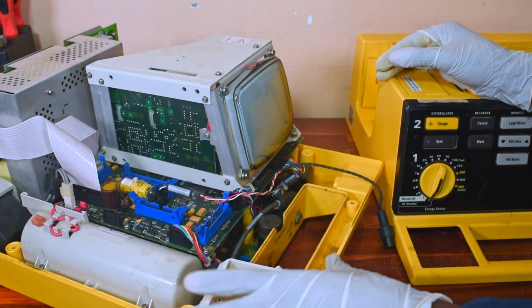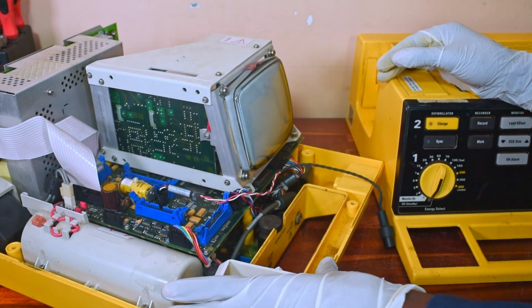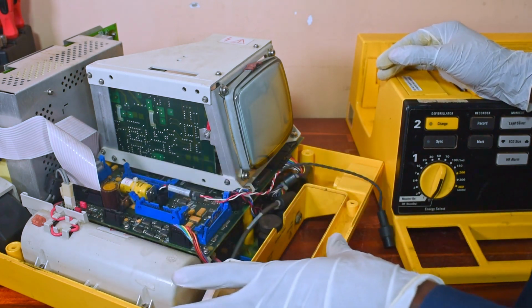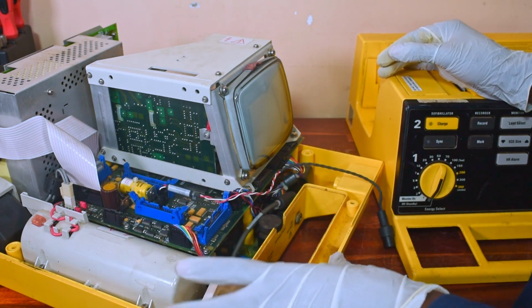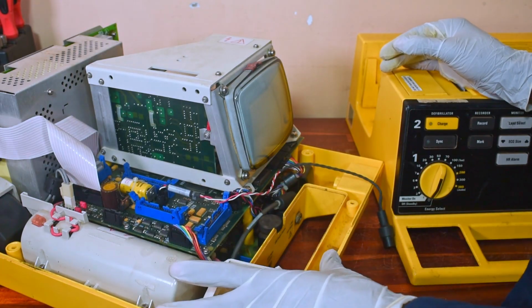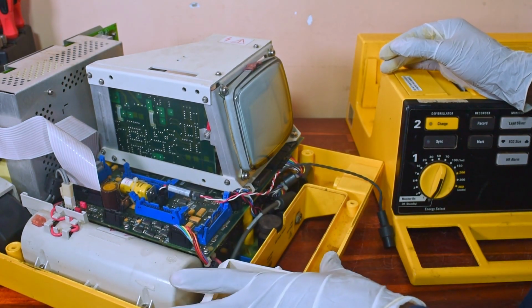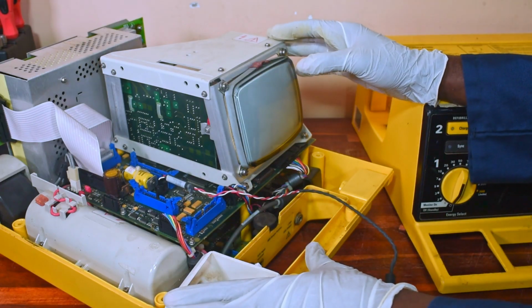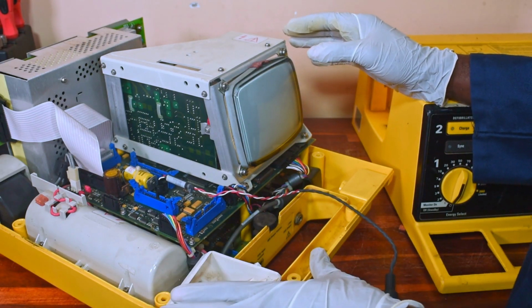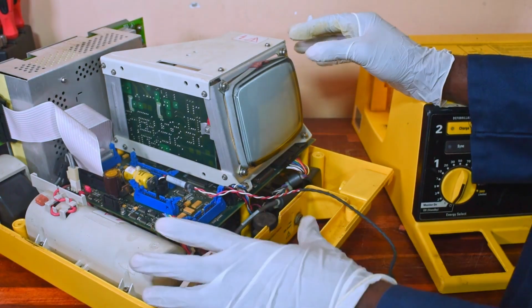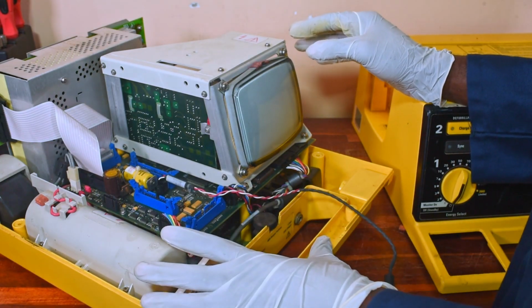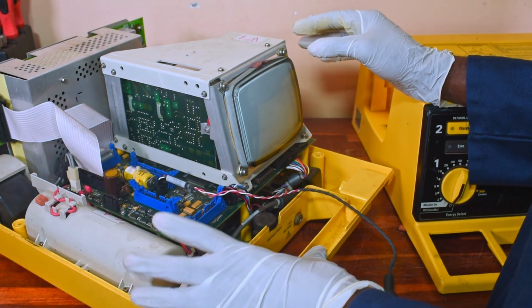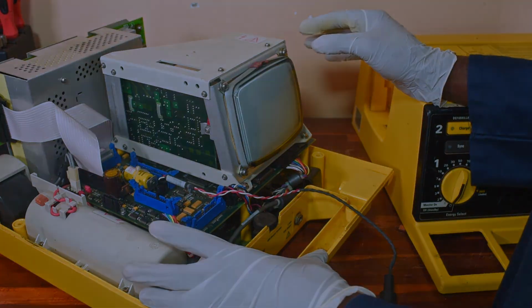ECG data is acquired using ECG leads. The data is then digitized by the ECG front-end board and then fed to the main control board, where it is processed by the digital signal processor. Once processed, the data is sent to the monitor processor for monitoring. Note that the fully charged battery can continuously sustain this mode for about 2.5 hours.